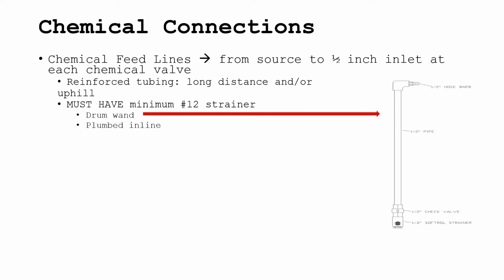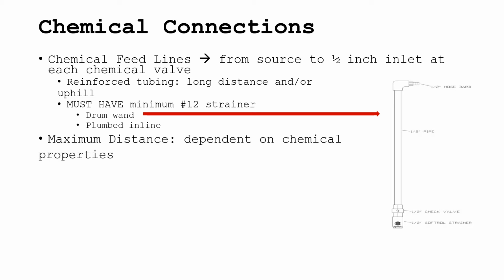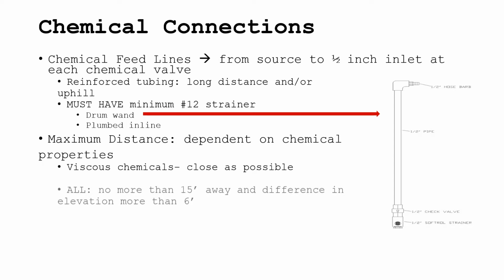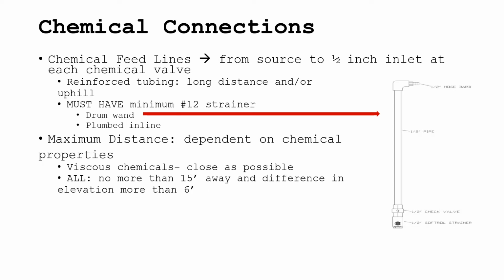If the strainers are plumbed in-line, it is recommended to have a shut-off valve on either side to allow for easy cleaning. The maximum distance for the feed lines depends on chemical viscosity and the difference in elevation. Viscous chemical should be kept as close to the unit as possible, but all chemicals should be no more than 15 feet away from the Catalyst LTLF system and should not allow the difference in elevation between the storage unit and the system to be more than 6 feet. Note, chemical viscosity should be no more than 400 centistokes.